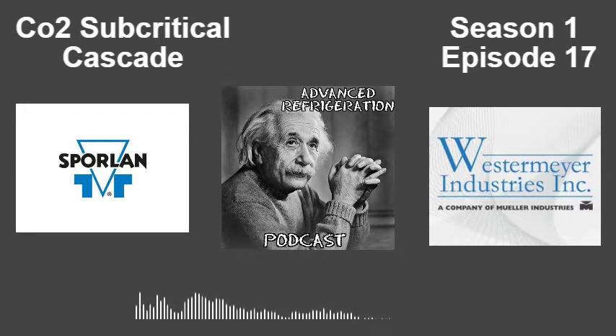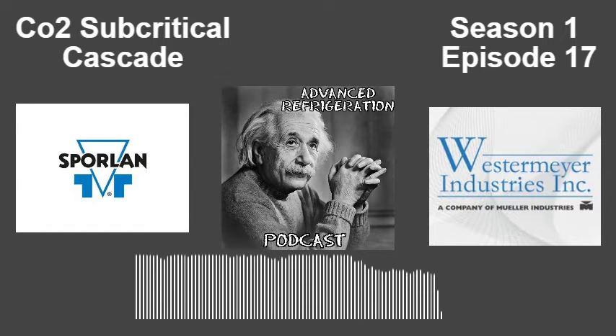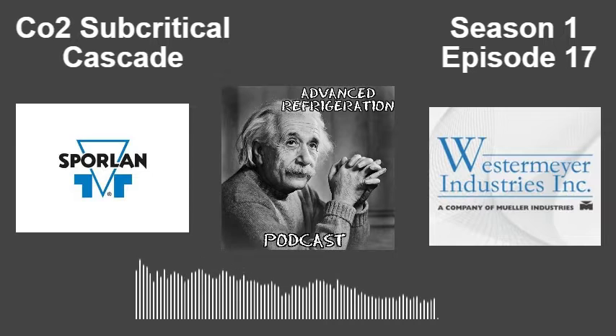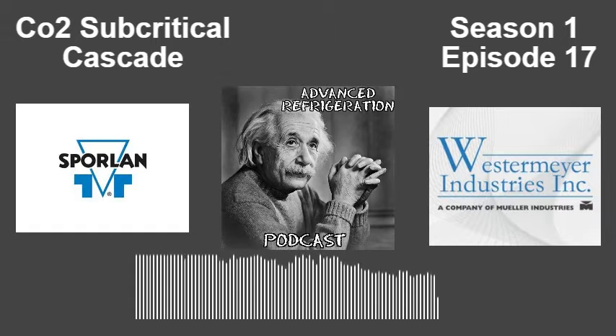Absolutely. So Cascade subcritical CO2 is a lot like pumped liquid. You're trying to control a lower temp SST to maintain a certain pressure, a certain SST as far as your CO2 side. Typically, on most racks that are set up, you're trying to maintain anywhere from 20 to 25 degree CO2 going down all your cases. That is dependent on what your medium temp side is. These systems have to be balanced.